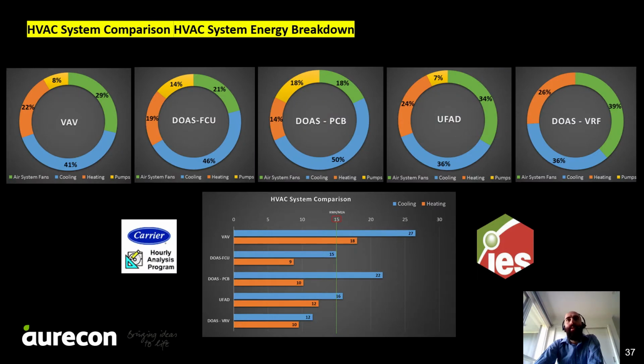The next important step for HVAC system design was to find opportunities to further improve HVAC system energy efficiencies. We looked into HVAC system components and how we can improve our design. Our simulation suggested that after compressors and heat rejection systems, fans and pumps are the biggest energy consumer of the HVAC system. So we adopted a new strategy to reduce pressure drops across piping and ductwork network in the building.